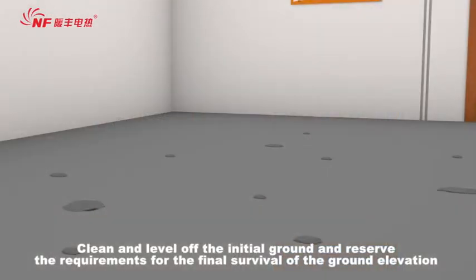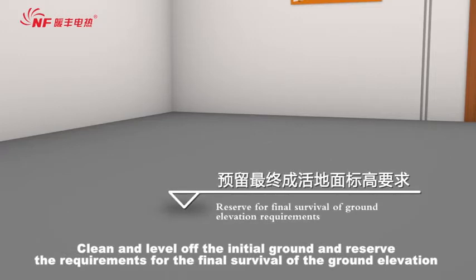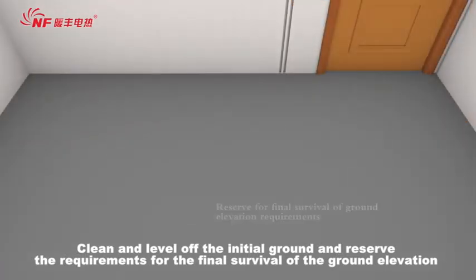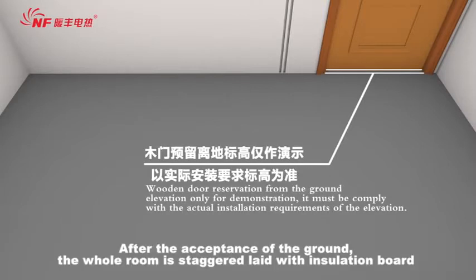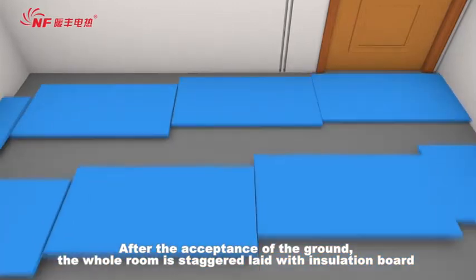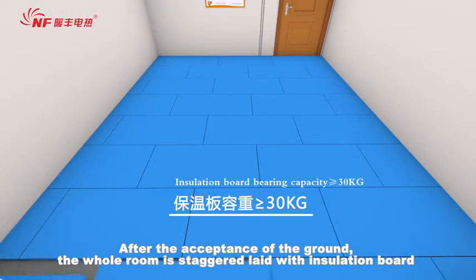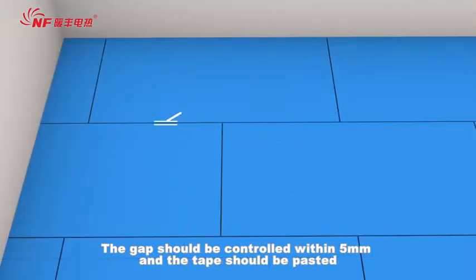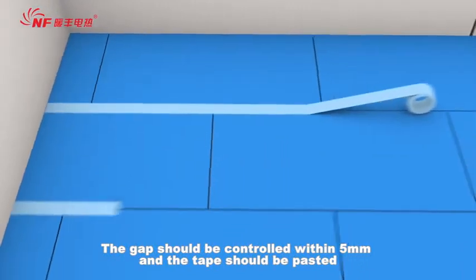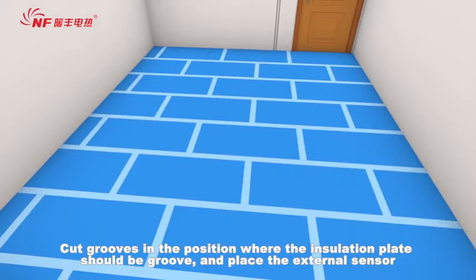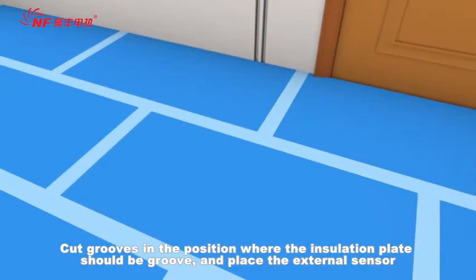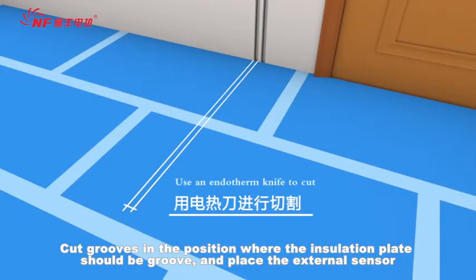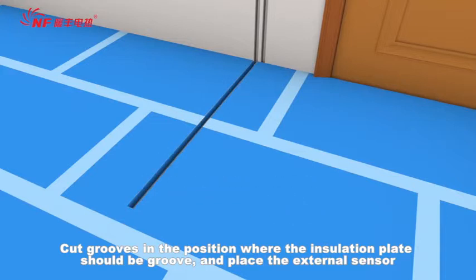Clean and level the initial ground and reserve the requirements for the final ground elevation. After the acceptance of the ground, the whole room is laid with insulation board. The gap should be controlled within 5 mm and the tape should be pasted. Cut grooves in the position where the insulation plate should be grooved and place the external sensor.